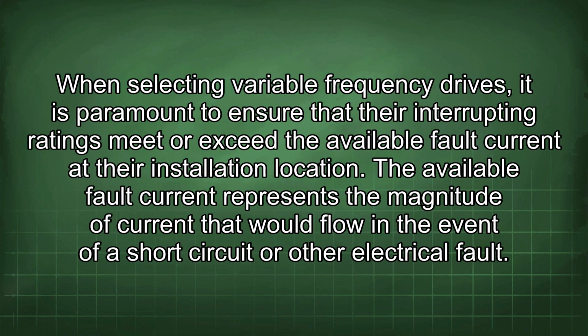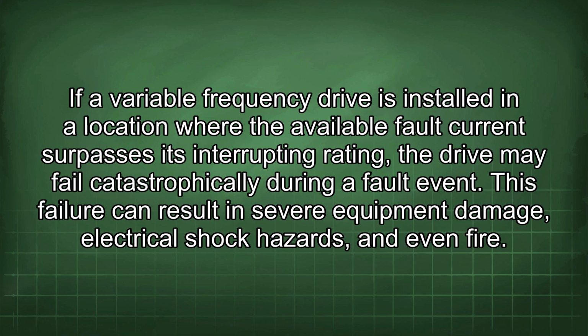When selecting variable frequency drives, it is paramount to ensure that their interrupting ratings meet or exceed the available fault current at their installation location. The available fault current represents the magnitude of current that would flow in the event of a short circuit or other electrical fault. If a variable frequency drive is installed in a location where the available fault current surpasses its interrupting rating, the drive may fail catastrophically during a fault event. This failure can result in severe equipment damage, electrical shock hazards, and even fire.